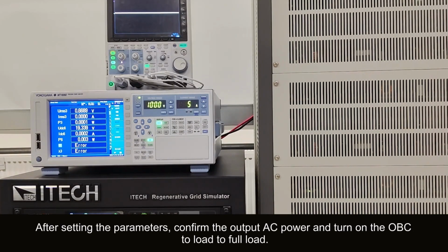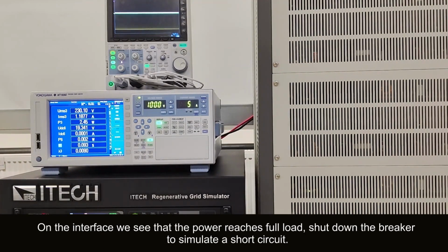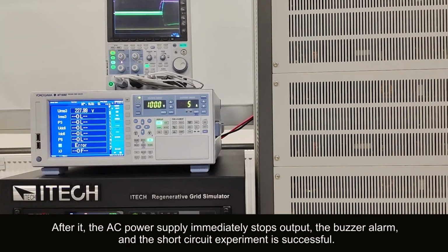After setting the parameters, confirm the output AC power, and turn on the OBC to load to full load. On the interface, we see that the power reaches full load. Close the breaker to simulate a short circuit. After that, the AC power supply immediately stops output, the buzzer alarms, and the short circuit experiment is successful.